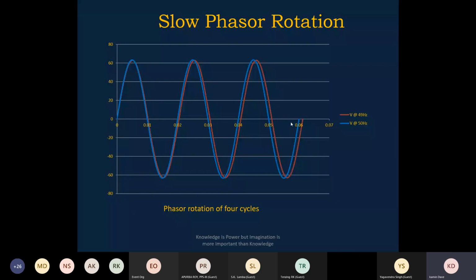When we try to match the frequencies, 49 hertz, 49.5 hertz, and the grid frequency is 49.97 hertz, and we match with 49.97, 49.99, then the phasor rotation is very accurate, close to the 49.97 hertz grid frequency, and it becomes very slow in that case. Here you see that when the difference increases, sometimes when you do 49 hertz, what will happen in a synchroscope? It will go faster, then slower, faster, slower, because the windowing will be matched in such a way that over a period, 1 second window, another 1 second window, another 1 second window.